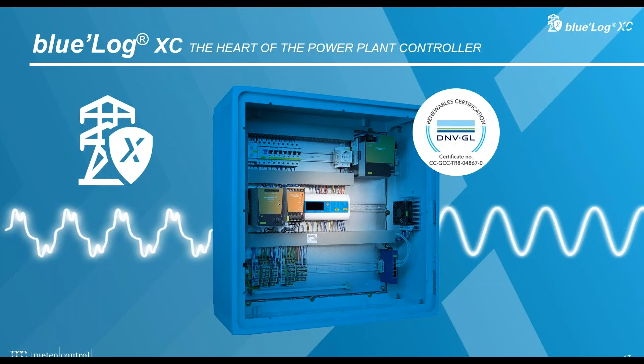So we do P and Q, for example. We have different modes of active and reactive power control. It can be a fixed value, a curve, an analog signal, or a value which always changes, sent by the grid operator. For reactive power, we have the power factor and reactive power control. A new feature is frequency control, so the active power will be reduced depending on the frequency, for example.